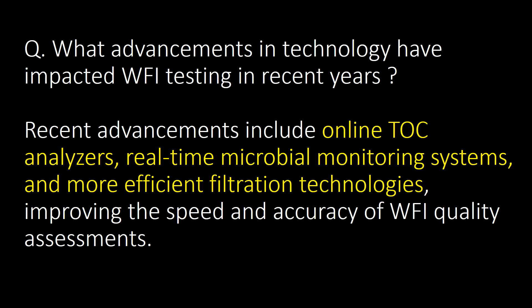Last and very important question: what advancements in technology have impacted WFI testing in recent years? Recent advancements include online TOC analyzers, real-time microbial monitoring systems, and more efficient filtration technologies, improving the speed and accuracy of WFI quality assessments.